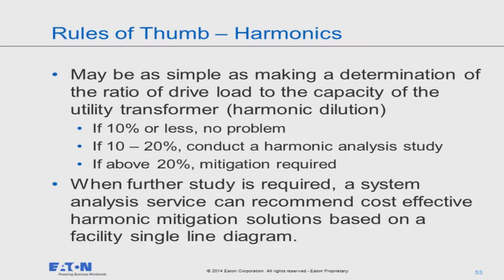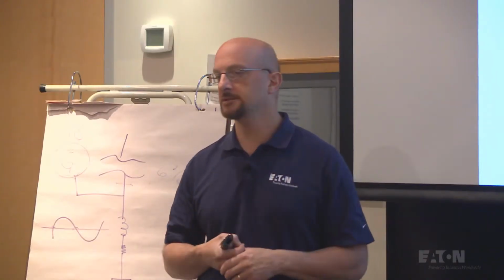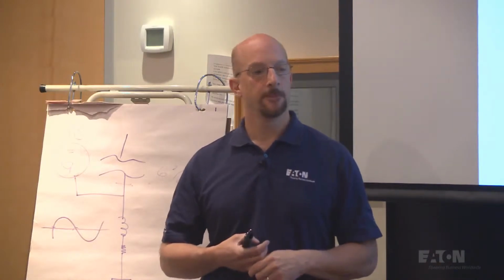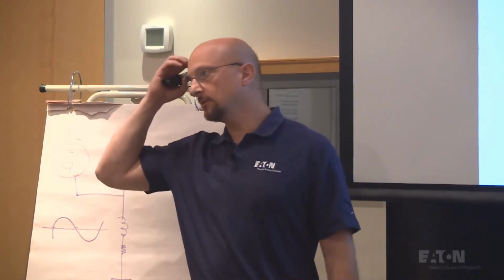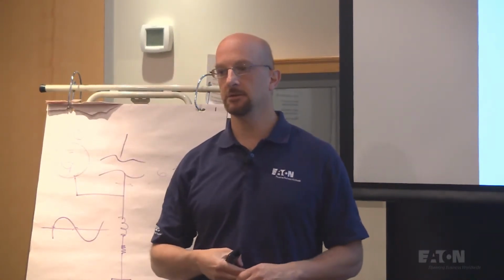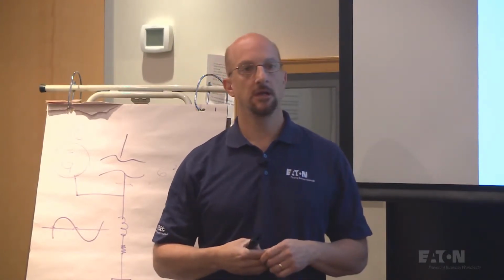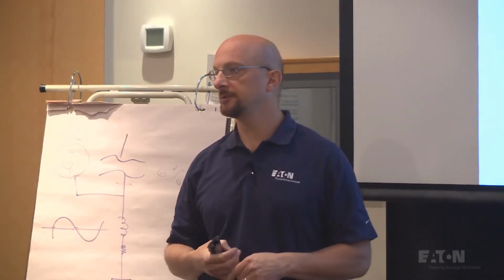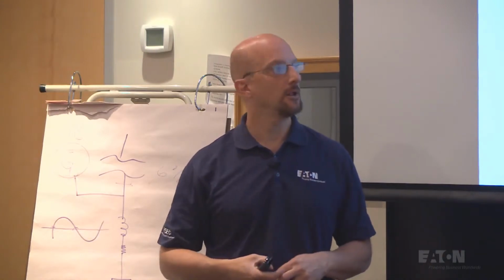Kind of a rule of thumb for harmonics: if you have less than 10% of your transformer load as harmonic load, it's probably not an issue. At 10 to 20%, you probably want to do an analysis, and above 20%, more than likely you want to do a study. And simulating this stuff is not always easy. It's dependent on what the customer might believe the load is, what you might believe the load is. It's not always evident, so you have to kind of figure that out.